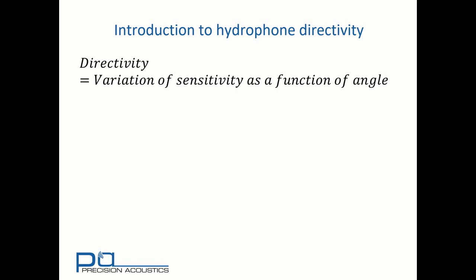This is the variation of a hydrophone sensitivity as a function of angle. Whilst angle of incidence is important, it's not the only factor influencing directivity. Directional response also depends upon sensor radius and wave number, which in turn means there's a dependency on wavelength and thus on frequency and speed of sound of propagation in the medium of interest.